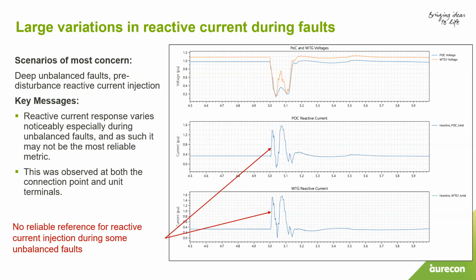The main point I want to convey here, because I've already shown you the variability, is that even if we assume the response is not lower than when it started, the challenge is what point I should be looking at. If I look at 5 milliseconds before or after, it might give me a very different result. So how can I use a fairly linear response, which is prescribed, whether in Australia, Germany, Europe or the US, since it all follows the same principles? How can I make sense of it? If I look at 5 milliseconds after, it could be 100% different. Is it success or failure? How do I know?